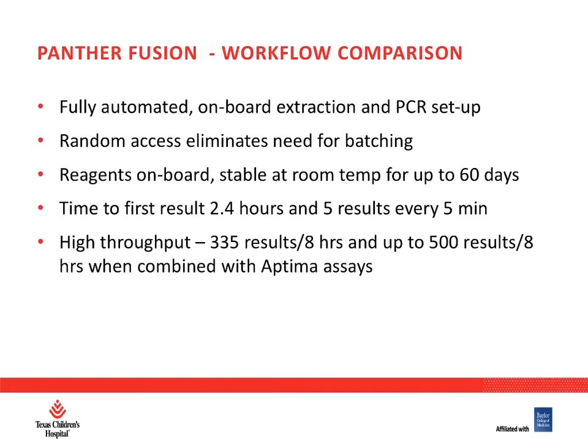So it really allows us to do it in a much more automated fashion with onboard extraction. As I said, we had been doing the MagNA Pure 96, pipetting all of that, making our master mixes, going to 96-well plates. So all of that now is automated and it's performed on board in addition to the PCR setup. And so it does have the random access capability.